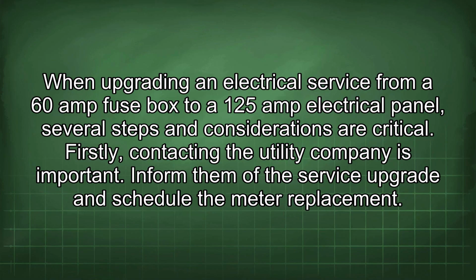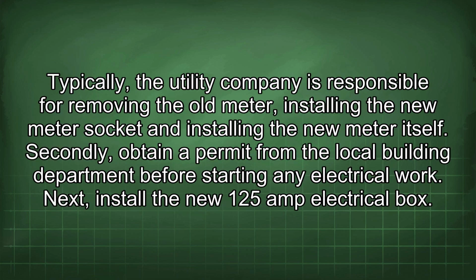When upgrading an electrical service from a 60-amp fuse box to a 125-amp electrical panel, several steps and considerations are critical. Firstly, contacting the utility company is important. Inform them of the service upgrade and schedule the meter replacement. Typically, the utility company is responsible for removing the old meter, installing the new meter socket, and installing the new meter itself. Secondly, obtain a permit from the local building department before starting any electrical work.